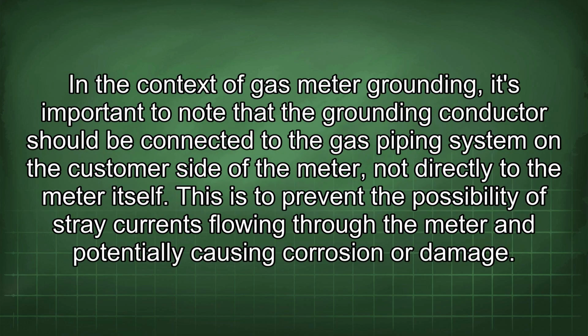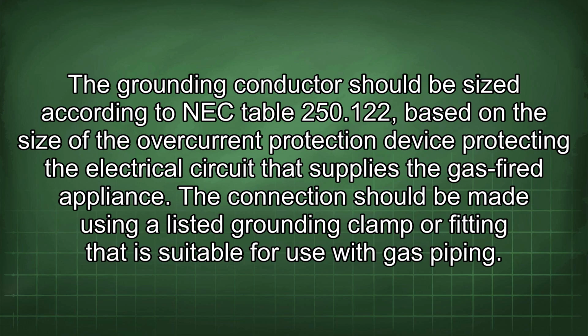In the context of gas meter grounding, it's important to note that the grounding conductor should be connected to the gas piping system on the customer side of the meter, not directly to the meter itself. This is to prevent the possibility of stray currents flowing through the meter and potentially causing corrosion or damage. The grounding conductor should be sized according to NEC Table 250.122, based on the size of the overcurrent protection device protecting the electrical circuit that supplies the gas-fired appliance. The connection should be made using a listed grounding clamp or fitting that is suitable for use with gas piping.